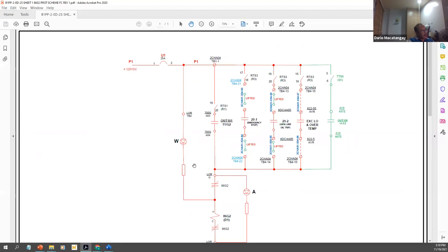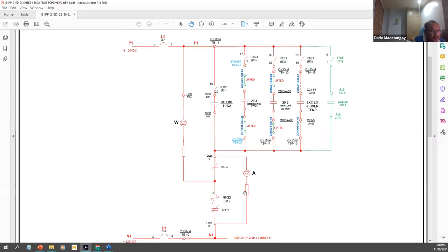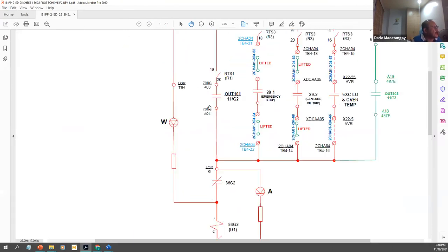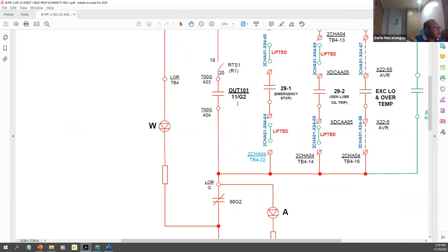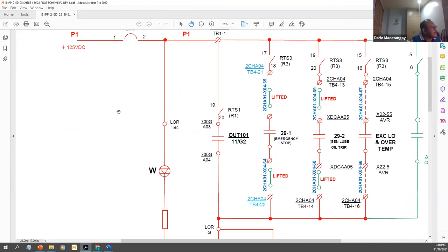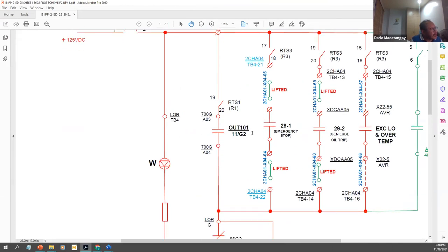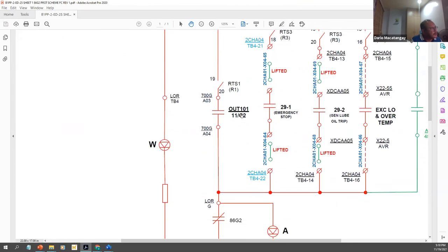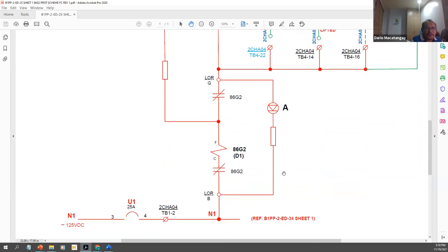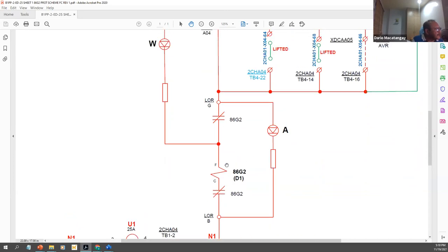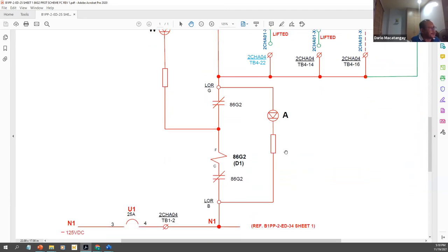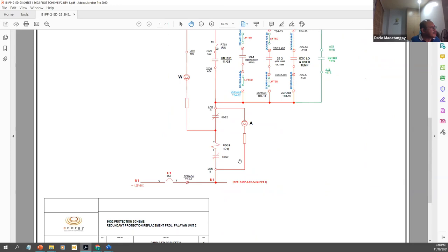Okay, see this, this is a lockout relay, and a lockout relay operates and then locks out the contact. It has a coil and contacts. So this one is a contact of the relay, the output 101, out 101. This is a microprocessor-based relay, okay? So when the relay actually sees the fault, the output, out 101 of the relay will close, okay? And when it closes, it actually energizes the lockout 86G2, okay? The 86G2, once there's a voltage here, it is going to trip. And when it trips, it's going to trip the associated contact and trips a breaker.